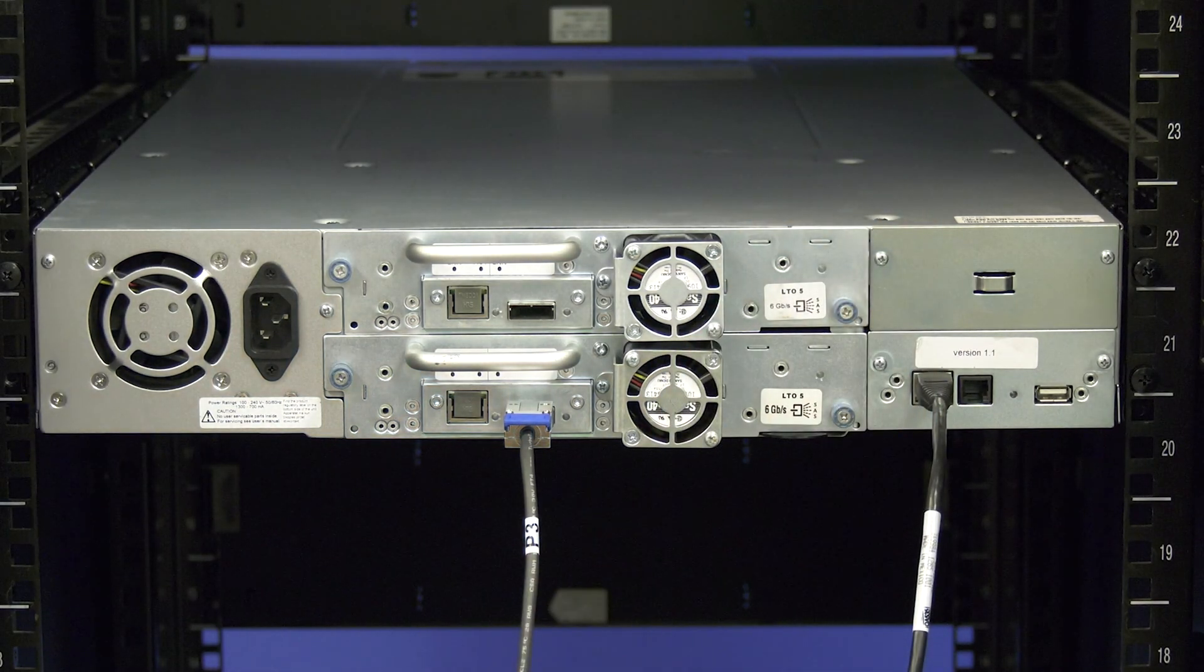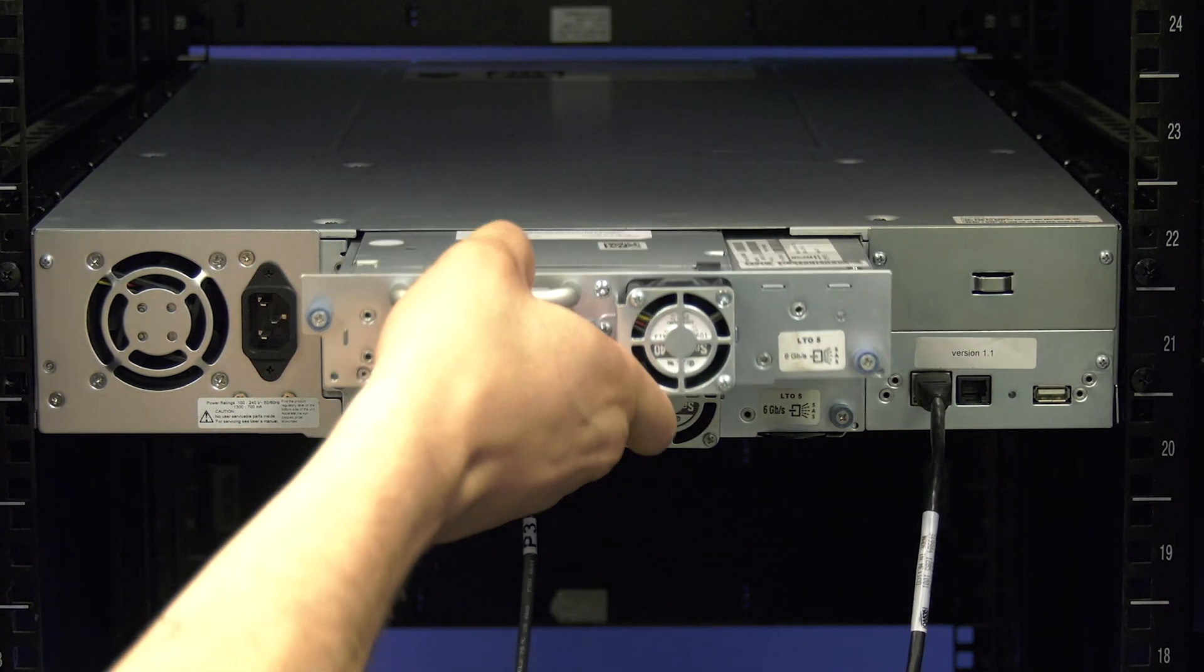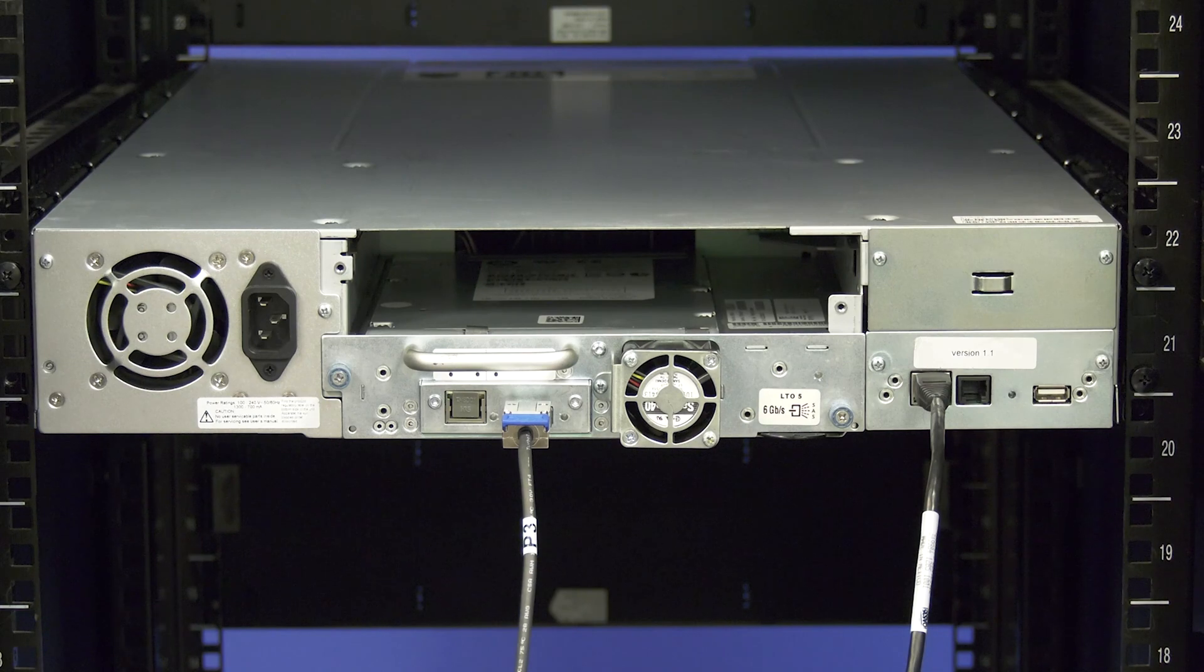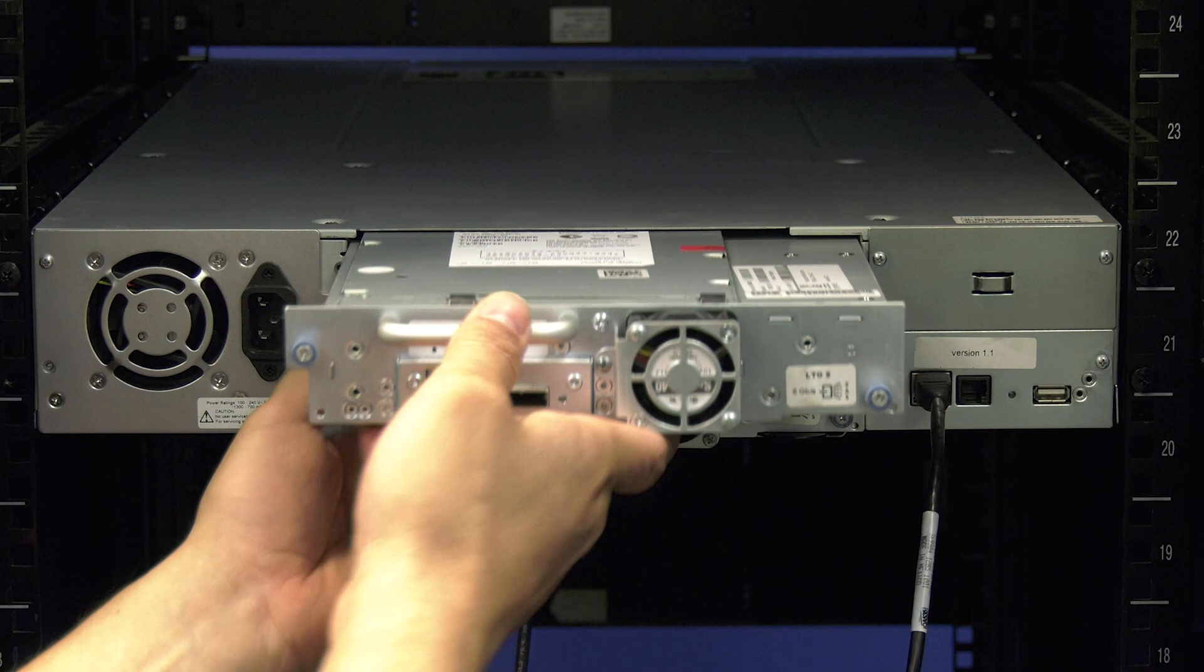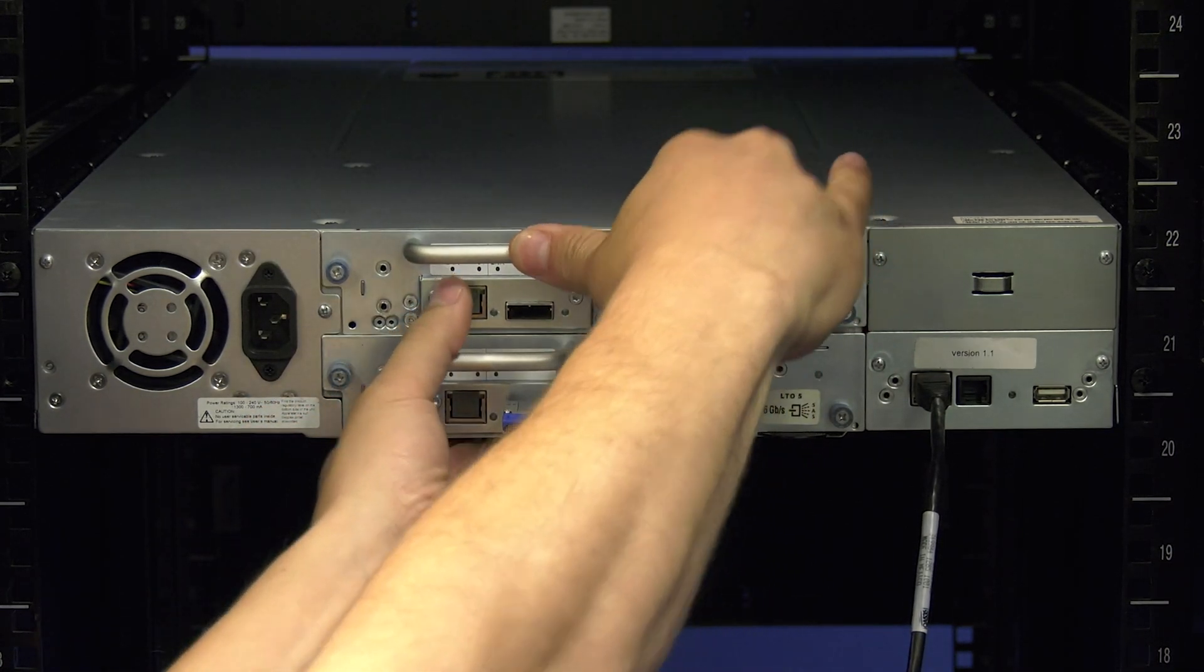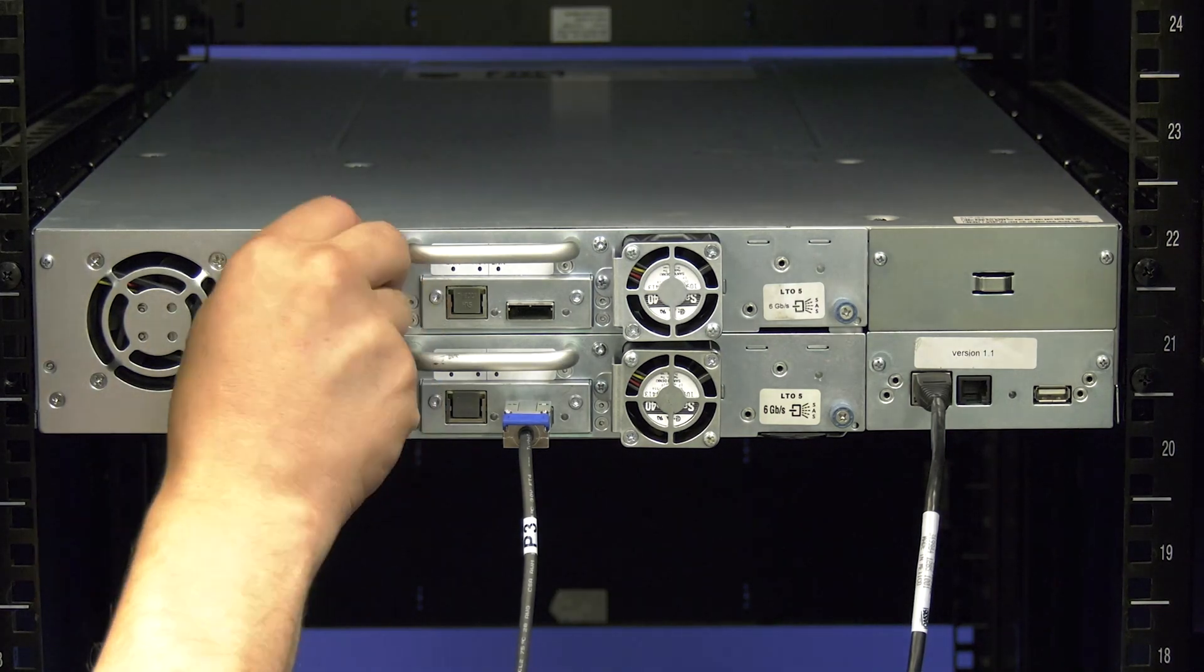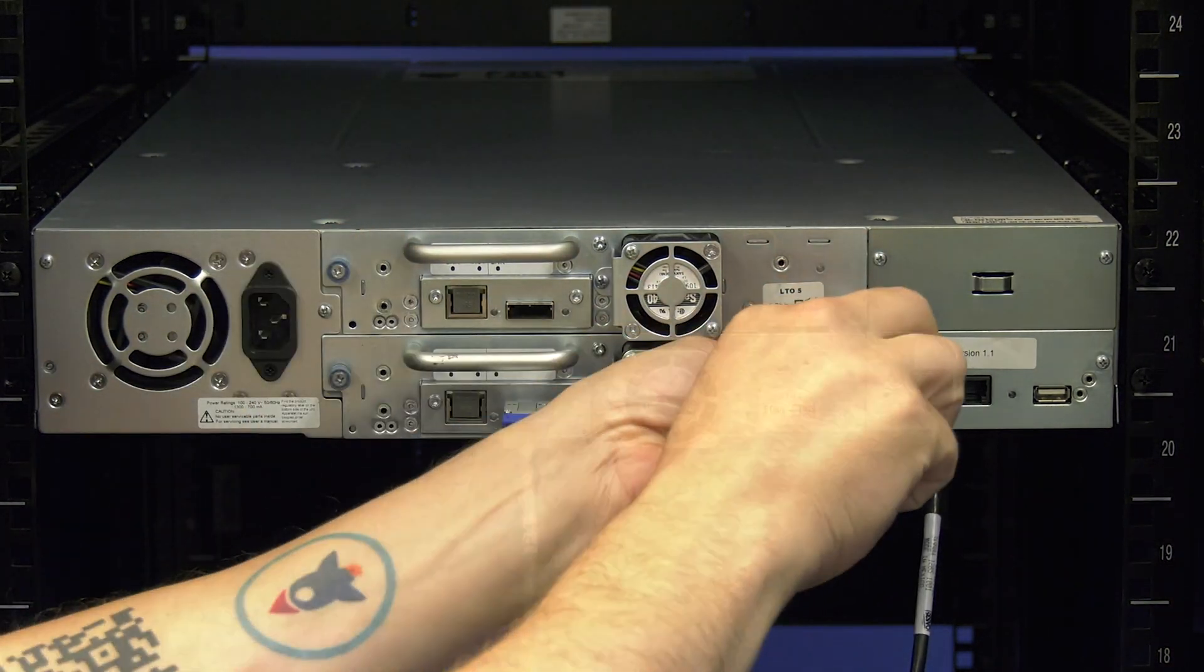Once all thumb screws are loosened you can pull the drive straight back and out of the library. You are now ready to install the replacement. Carefully line up the replacement drive with the black guide rails and the empty drive bay. Slide the drive in until you feel it make contact with the back plane of the library. Then push firmly to seat the drive completely and tighten down all thumb screws to secure the drive in place.